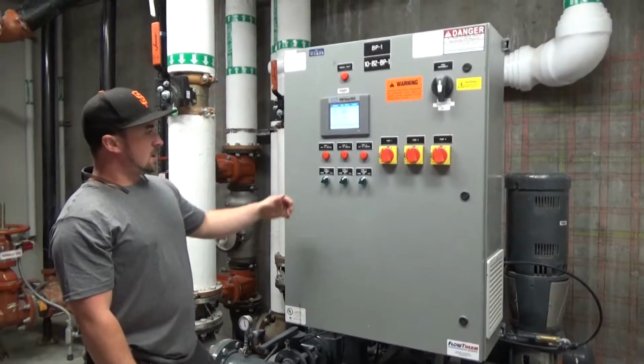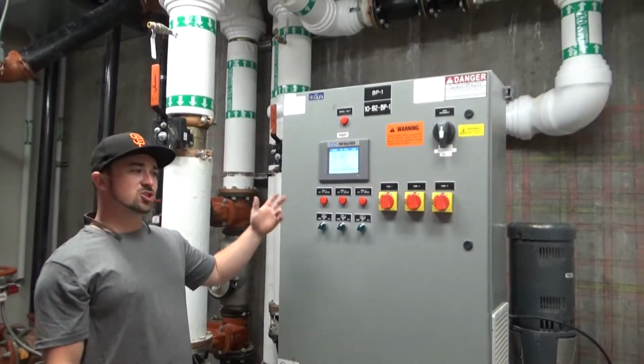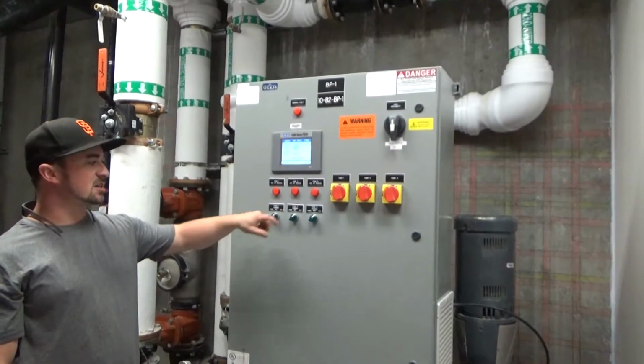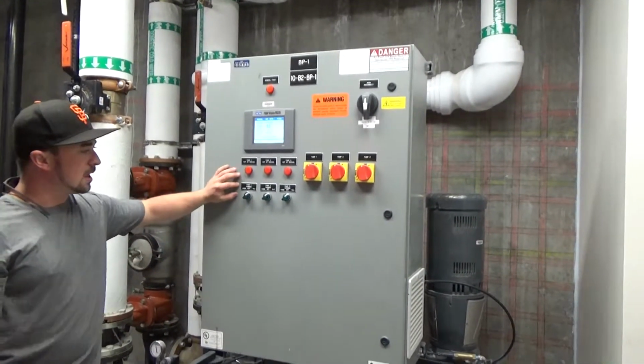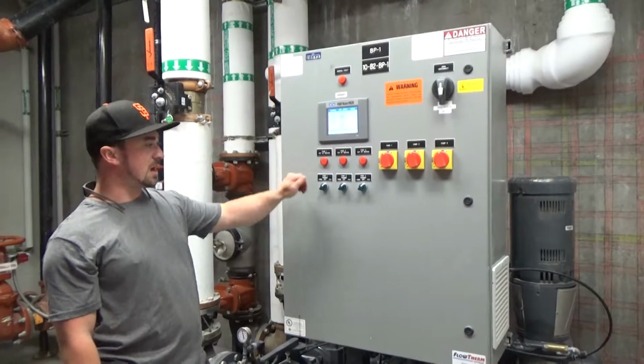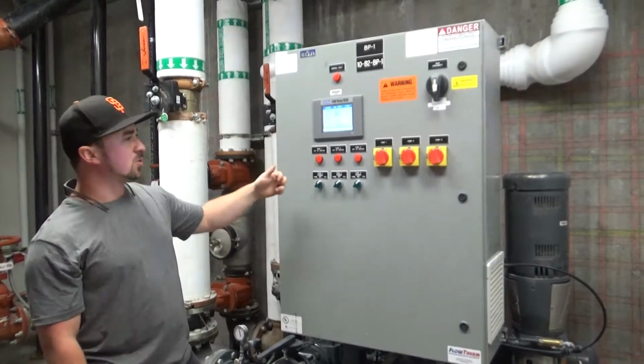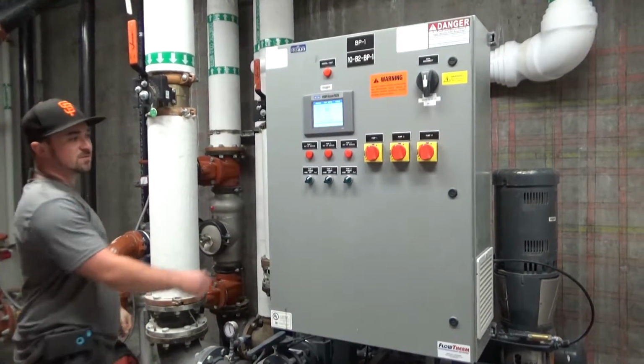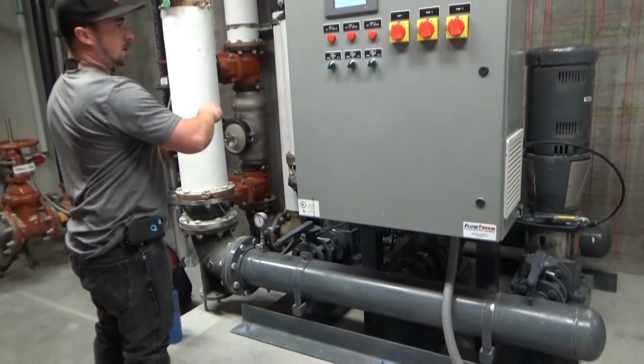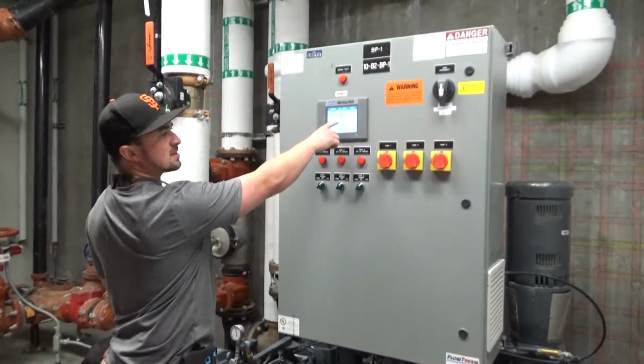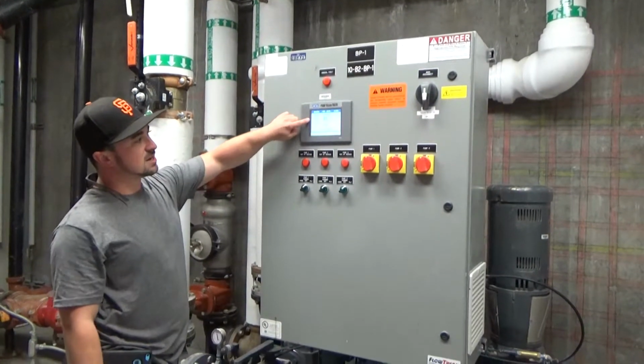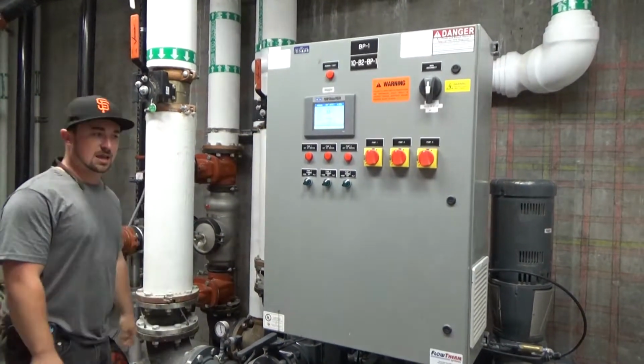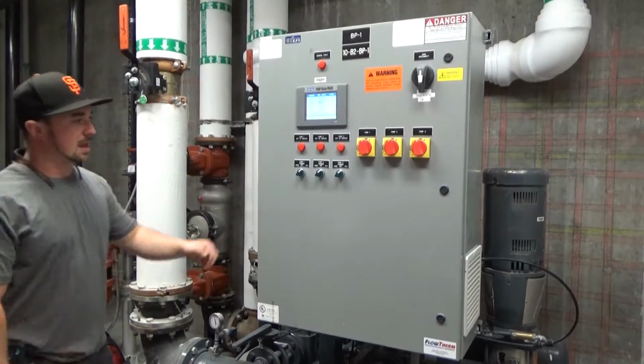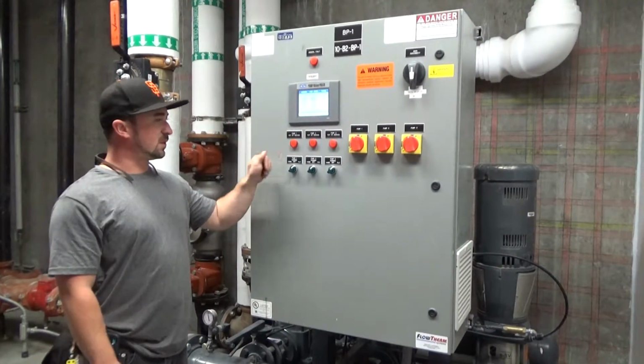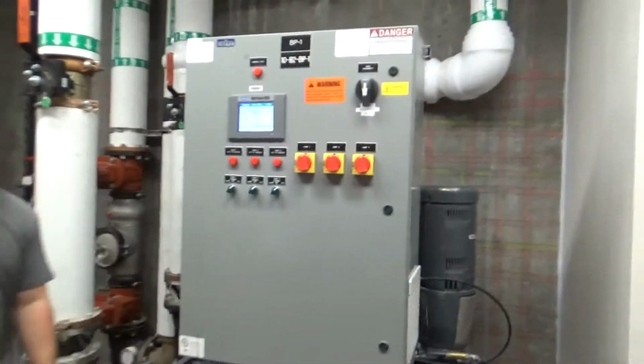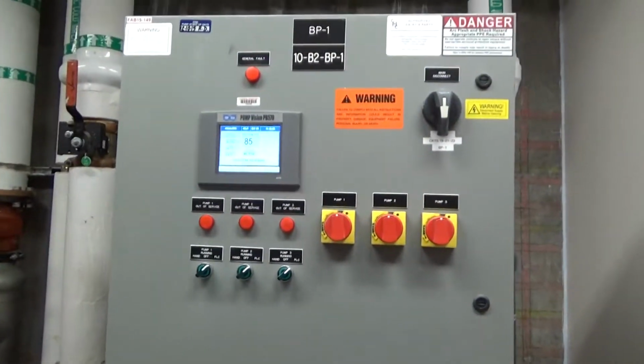So right here you have your HOA switch, hand-off-auto. We use PLC instead of auto, which can be kind of confusing to some people. But basically it's just hand. So hand mode is just one set speed. When we do startup on these, we set it so if you put it into hand, that one pump should be able to get you about 2 or 3 psi less than what your set point is. Your guys' set point is 85 psi. So say all the drives fail and you guys need pressure, you can flick it into hand, it should put you about 82, 83 psi, so you guys still have pressure up on the top floors.